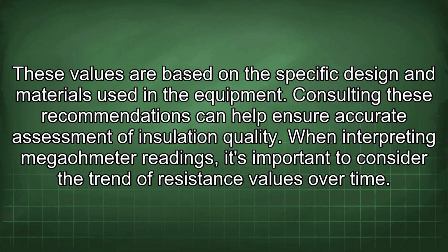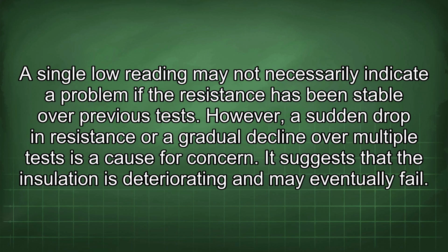When interpreting megaohmeter readings, it's important to consider the trend of resistance values over time. A single low reading may not necessarily indicate a problem if the resistance has been stable over previous tests. However, a sudden drop in resistance or a gradual decline over multiple tests is a cause for concern. It suggests that the insulation is deteriorating and may eventually fail.